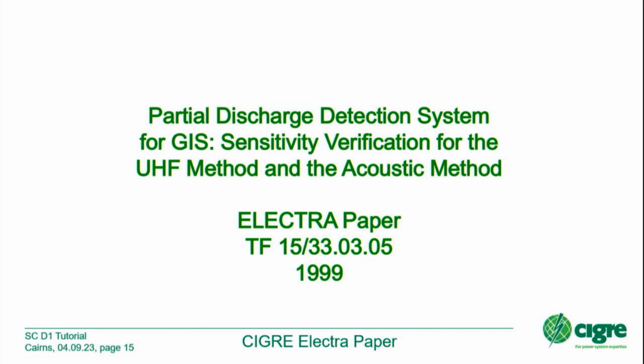And the CIGRE working group, here the task force 15/33.03.05, worked a few years, and they came up with a kind of sensitivity verification. It's not calibration. They were defining a set point, that in the laboratory you find the level in the UHF range which is equivalent to 5 picocoulomb.